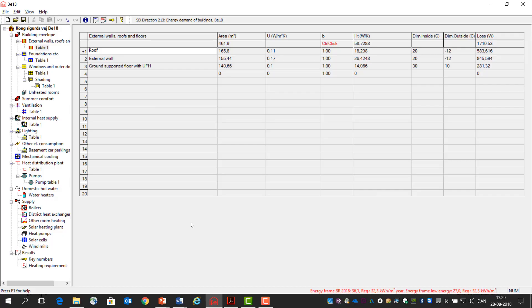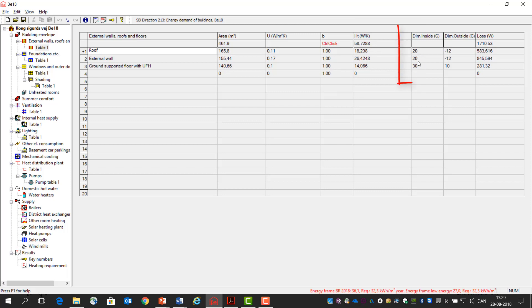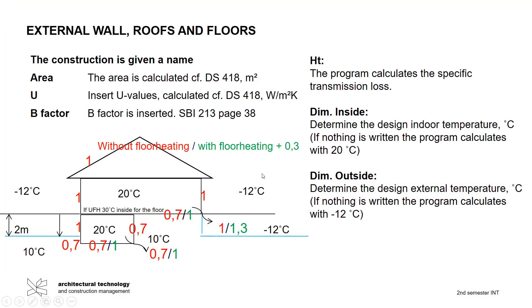And if we go back then we have the specific heat loss which the program calculates, and then we have the temperatures, and the temperatures we can also look up in the same table as before. So you can see here but normally we have 20 and minus 12 outside. In the soil under the house we have 10 degrees.